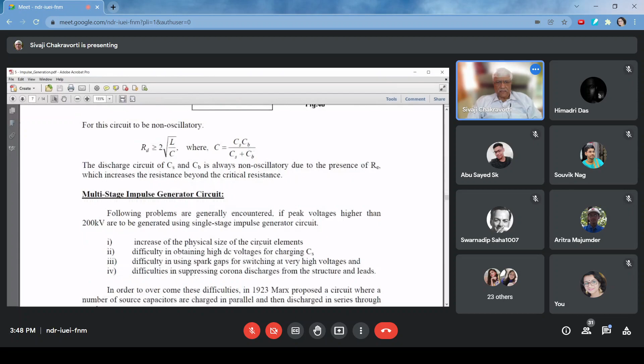As discussed in both AC and DC generation, if our output voltage becomes high, typically higher than 200 kV, using a single stage impulse generator becomes extremely difficult. This is because it increases the physical size of circuit elements like C and R, and we also need a correspondingly high voltage DC source. For example, a single stage impulse generator rated at 400 kV would need a 400 kV DC source, which becomes a real problem.